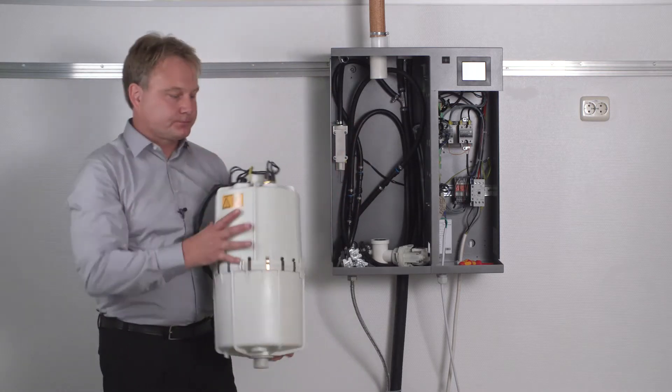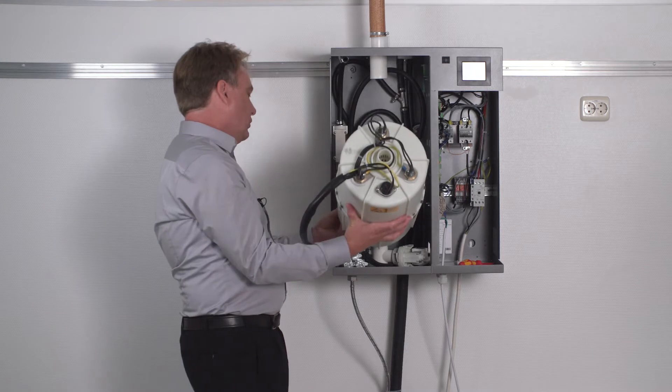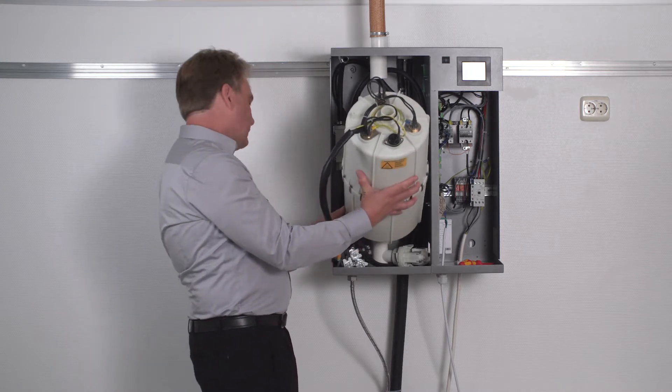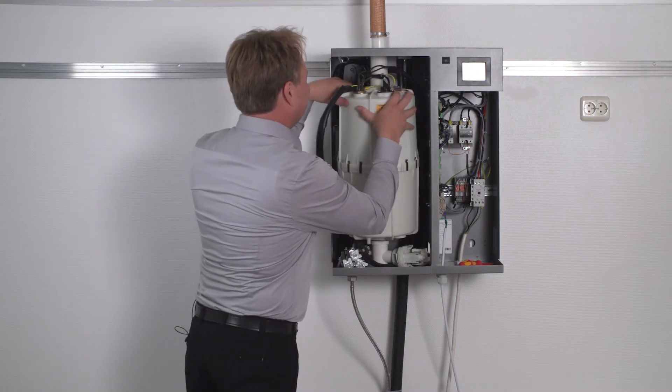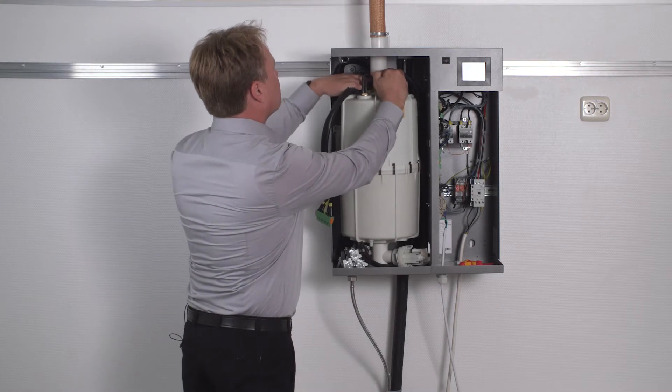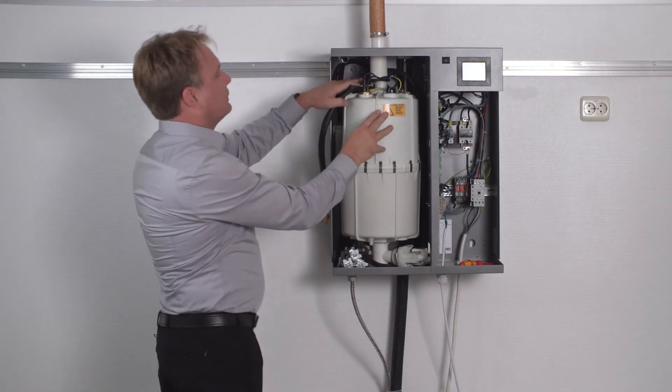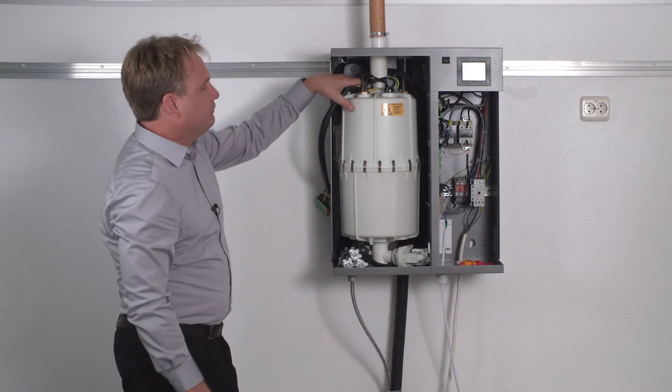Then I take the steam cylinder and just set it in by inserting it into the bottom of the cylinder base first, and tilt it a bit and turn. Please make sure all cables are unhindered, that they aren't squished anywhere.